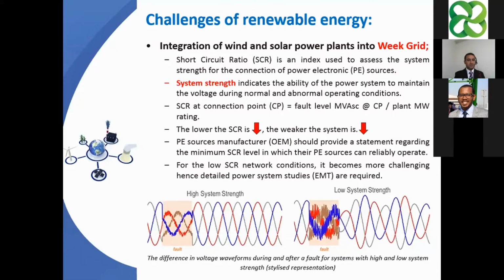So in a formula, the short circuit ratio at any point in the system is the fault level at that point divided by the plant ratings in megawatts or megavolt amperes connecting to the same point. So the conclusion here: the lower the short circuit ratio is, the weaker the system is. So our goal is to do our best to assess the short circuit ratio to identify the risk and mitigate it. In addition to that, the OEM or the power electronic source manufacturer should provide a clear statement regarding the minimum short circuit level in which their equipment can reliably operate.